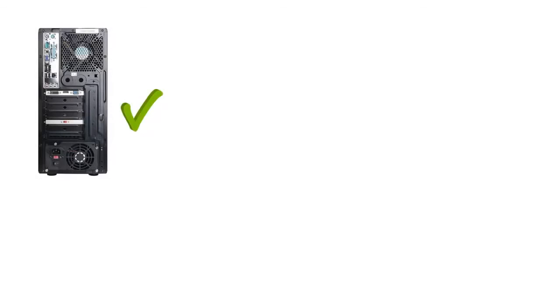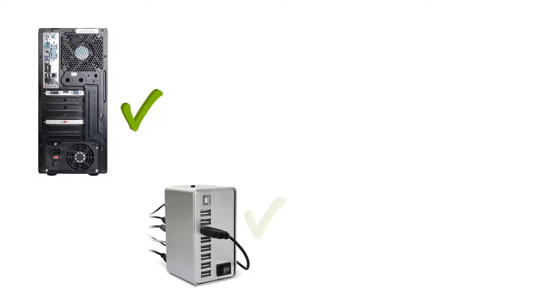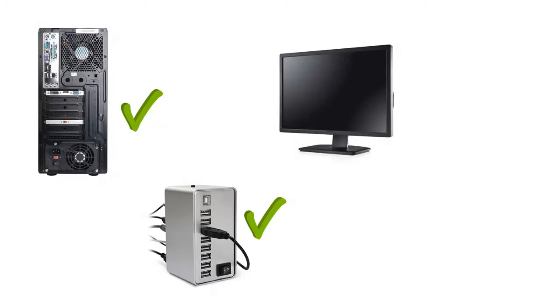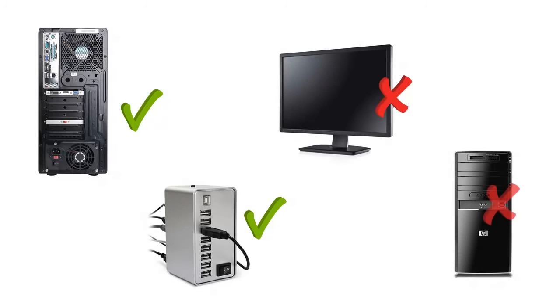It is important to use the USB ports on the back of the PC tower or a powered USB hub in conjunction with the RVG sensors to ensure signal data transfer quality. Do not plug the RVG sensor or the USB hub into a USB port on the monitor or the USB ports on the front of the PC tower.